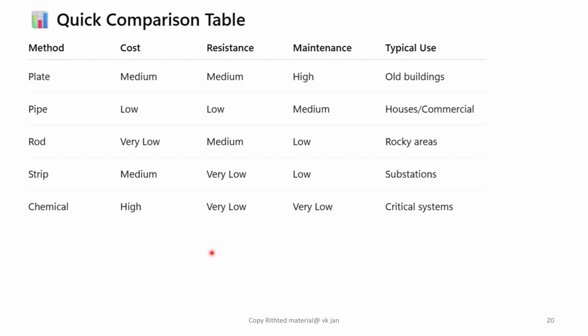Friends, at last I am putting up a table which compares all types of earthing systems: plate, pipe, rod, strip or chemical earthing. Chemical earthing is used in critical systems having very high cost. Strip earthing may be used in substations. Rod type of earthing is recommended for use in rocky areas. Pipe and plate earthing are the common methods, of which plate earthing has medium resistance and pipe provides low resistance, and it is used in houses and commercial installations. Plate type earthing had been used in old buildings.